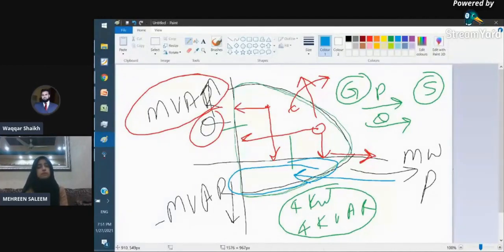Under normal operation, we always have active and reactive power flowing from the generator into the network. This is called overexcited operation of the generator, where the generator is providing active and reactive power towards the network. In both scenarios, if the generator is absorbing more reactive power, it will shift the operating point out of this region. When the point is crossing this area, it means more and more reactive power is drawn from the generator. If the point goes below the lower region, it means it is absorbing more and more reactive power. It is again dangerous to the generator.